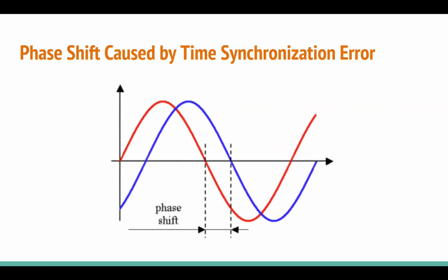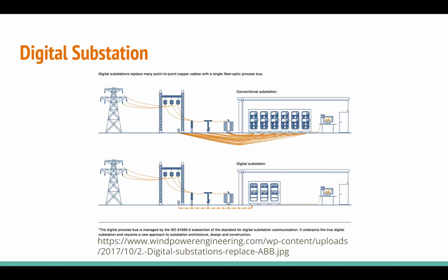Let me jump back a few slides to explain this better. In the past, with a conventional substation, if your Ethernet network went down, it wasn't the end of the world. It wasn't good, you needed to get it back working, but your company isn't losing a ton of money per minute while it's down. Basically, if your Ethernet network went down with a conventional substation, you lose your connection back to the control center and it won't understand what's going on with that substation. You can't send remote operations, but your protection is still working fine. Your IEDs monitoring current, voltage, and everything on the grid will operate just fine, and if you have a fault with too much current, it will still open the breaker. Everything will work just fine.